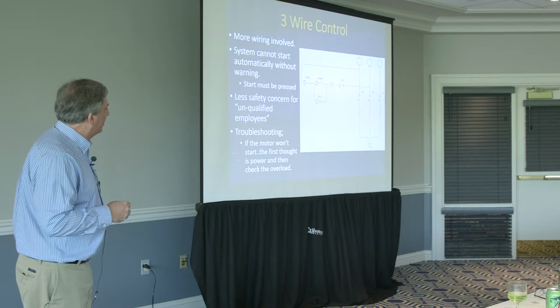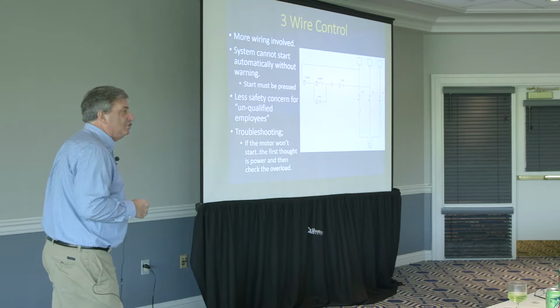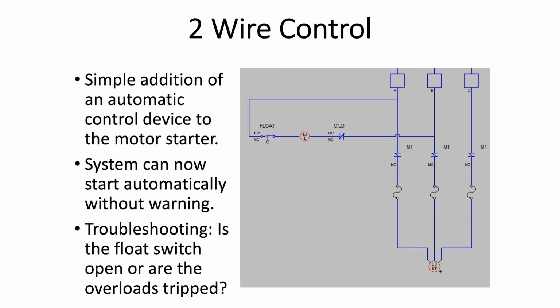Troubleshooting. If the motor won't start, the first thought is power, and then check the overloads. But if I go to 2-wire control with that float switch, now if that float switch is closed, the overloads kick out, and then they come back on automatically, that thing can still start up and run with no warning. Okay? So that becomes the issue.